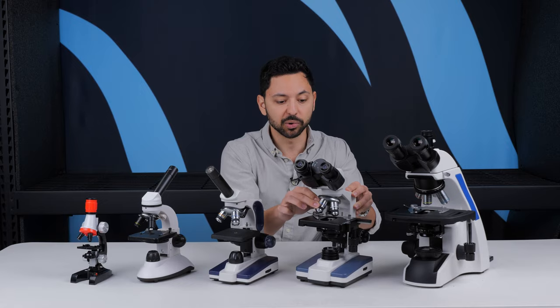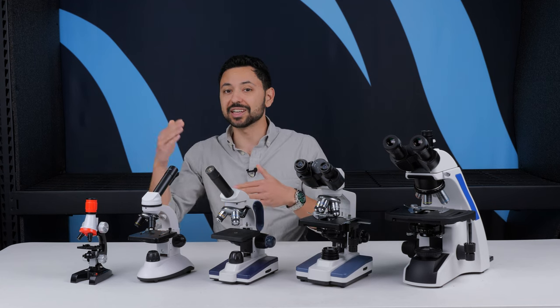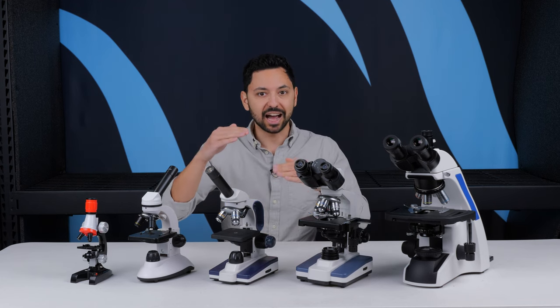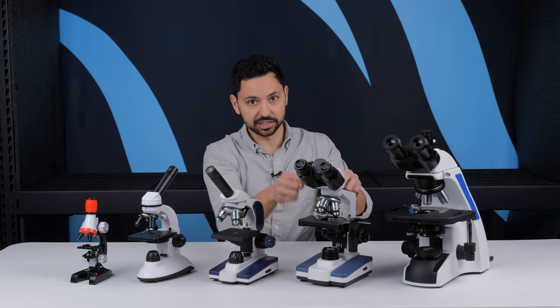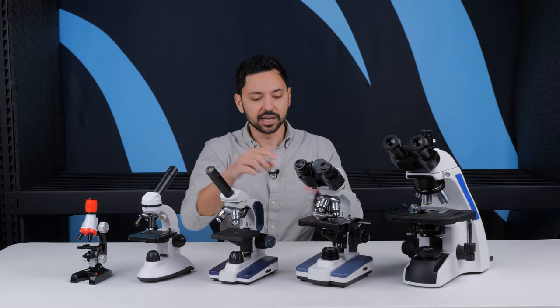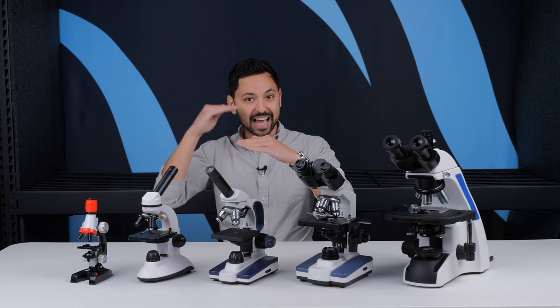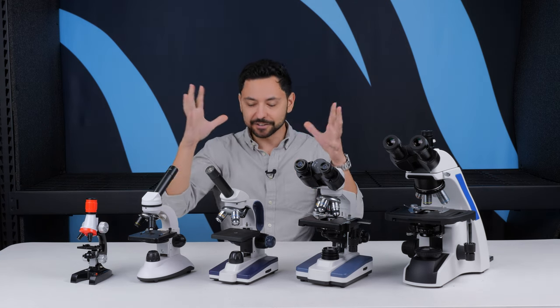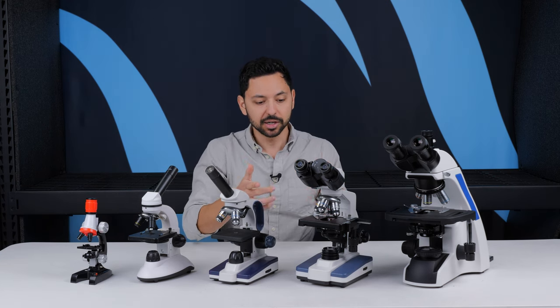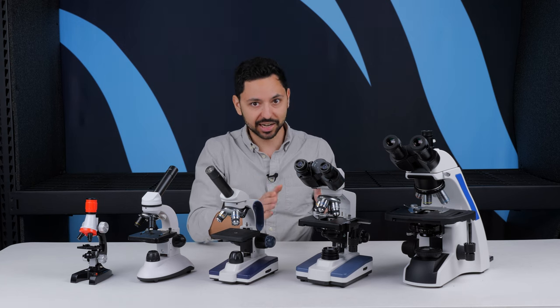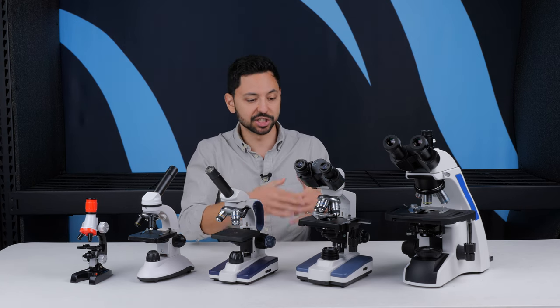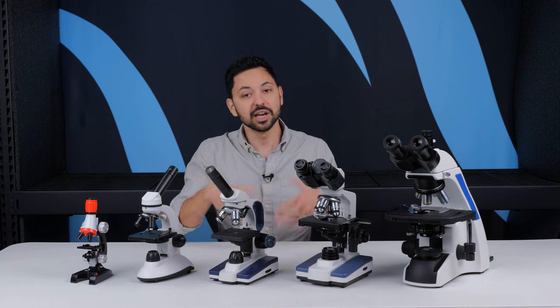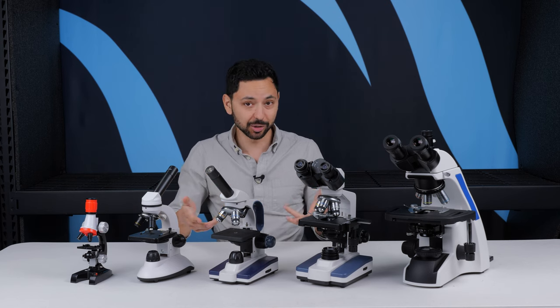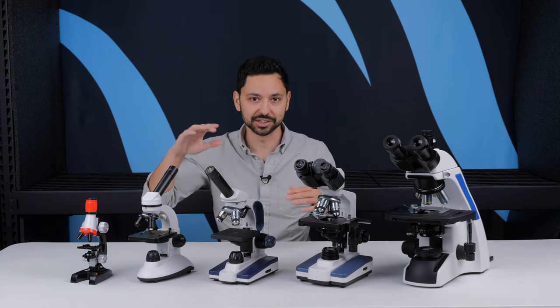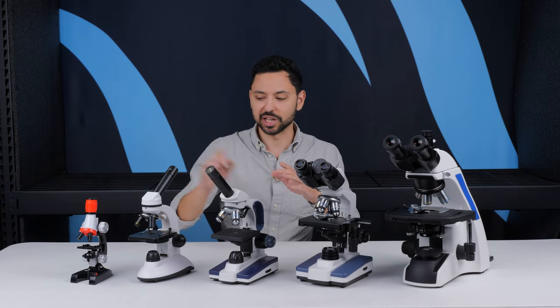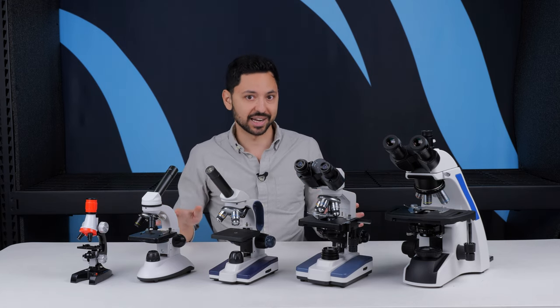The reason this is important is that once you get to higher magnification levels, having the lenses inside each objective exactly placed in a fixed spot relative to each other gives you much higher image clarity and precision. Compare that to a stereo microscope, which has a zoom knob on the side for continuous zoom. Compound microscopes do not have that.